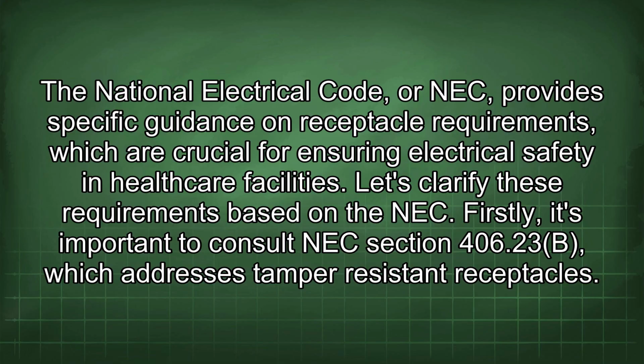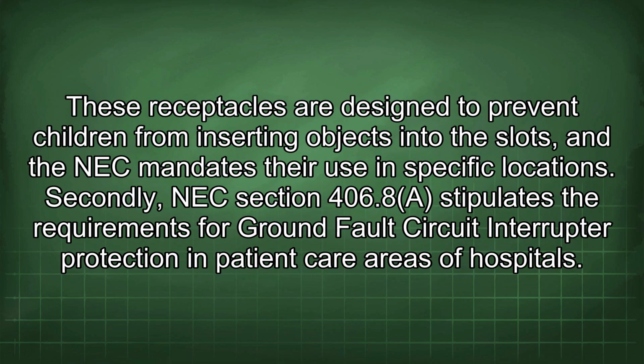Let's clarify these requirements based on the NEC. Firstly, it's important to consult NEC Section 406.23b, which addresses tamper-resistant receptacles. These receptacles are designed to prevent children from inserting objects into the slots, and the NEC mandates their use in specific locations.